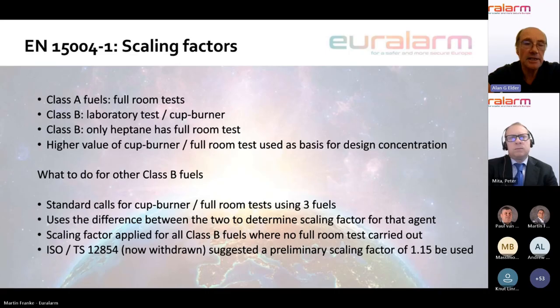Now, as written in the previous edition of the standard, it was only necessary to take a cup burner value. So let's say you had acetone as a fuel, and you carry out a cup burner examination, and you get a certain value for your extinguishing agent for acetone. That would be used as the basis of the design concentration.